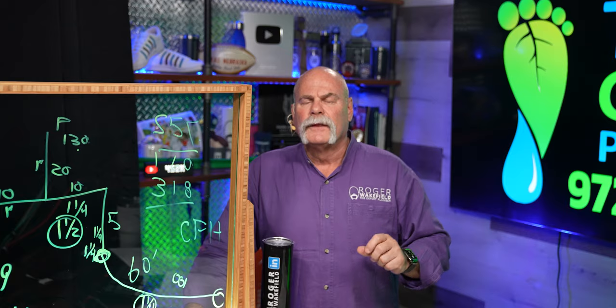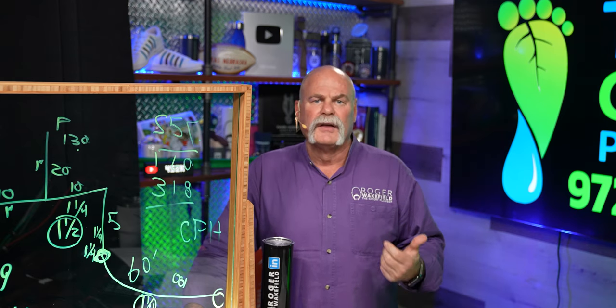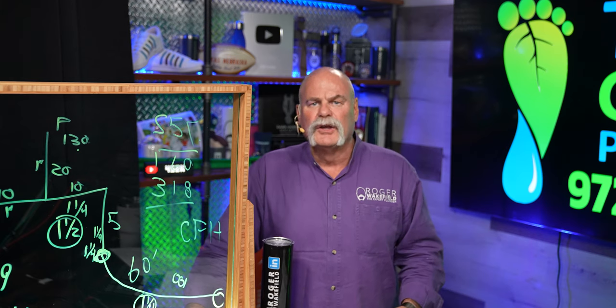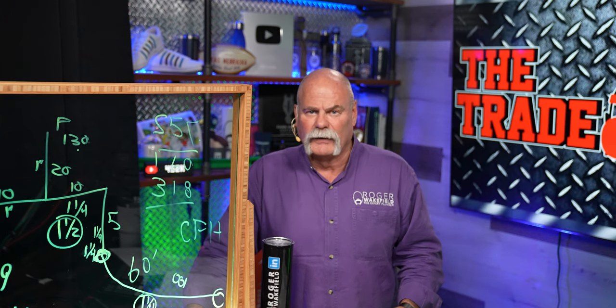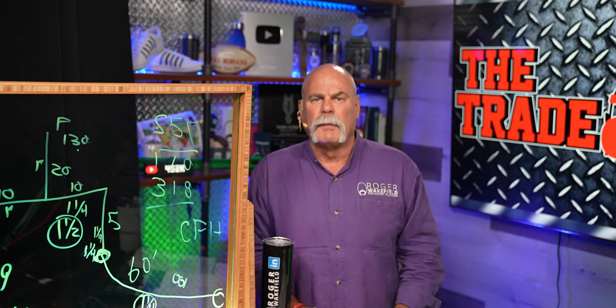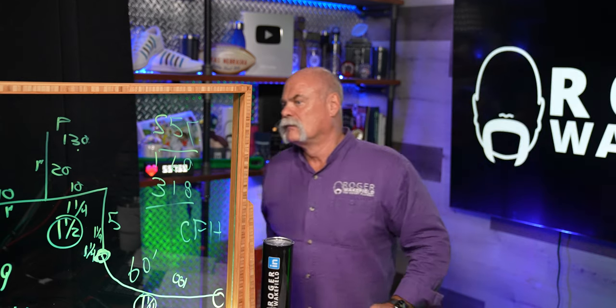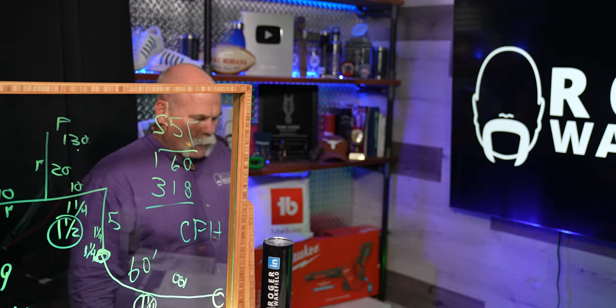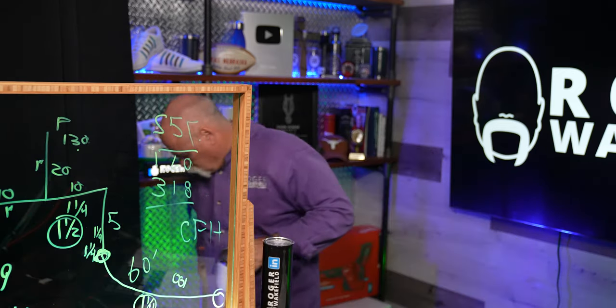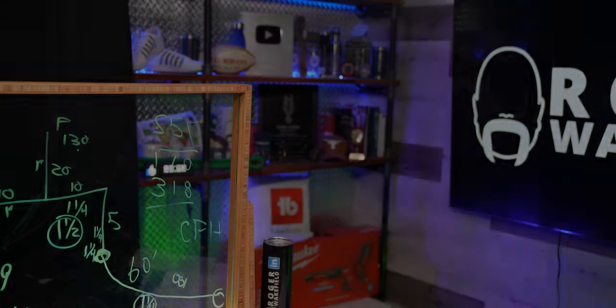When you do a tankless water heater installation, are you looking at everything? When you do a gas load calculation, are you figuring everything in? You can look at the plate on each fixture to see what's there; for any that don't have a plate, you may have to use an average. Make sure you understand gas sizing very well anytime you're adding any fixture. Learn where your charts are, know what you need to go by, and know your minimum pressures and pressure drop. This has been a gas load calculation chart — I hope it helps you out. I'm Roger Wakefield, Lead AP, helping you make more money in the trades.